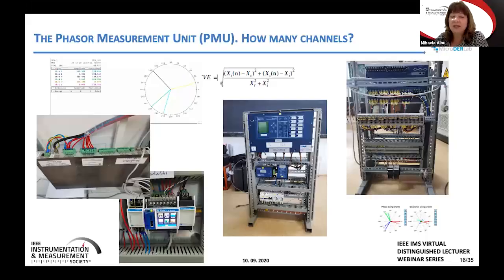We can see that we can have PMUs with a standard 3-phase voltage channel and 3-phase current channel, or PMUs much more complicated, like this one that has 2 separate 3-phase voltage channels and up to 8 configurable separate 3-phase current channels, which makes them suitable for measurements in substations with double bus bars and more lines.